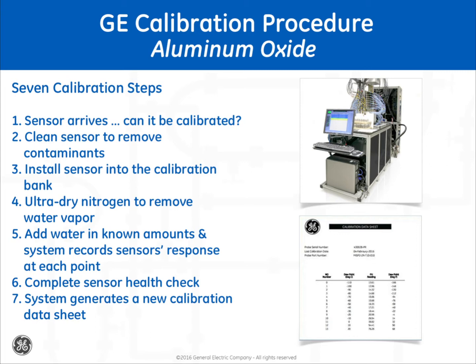5. Water vapor is added in known amounts, and the system records each sensor's response at each calibrated point. 6. The system interrogates the data collected for a complete health check of the sensor, including signal, noise, and sensitivity. 7. The system generates a new calibration data sheet for the sensor and programs any associated electronics with this data. This procedure is used for the initial calibration and all subsequent recalibrations. Other manufacturers may have similar procedures.